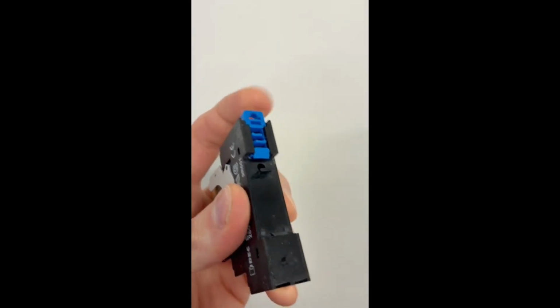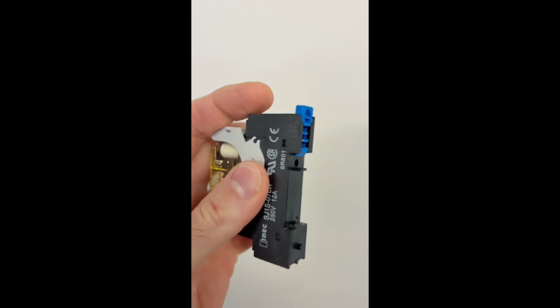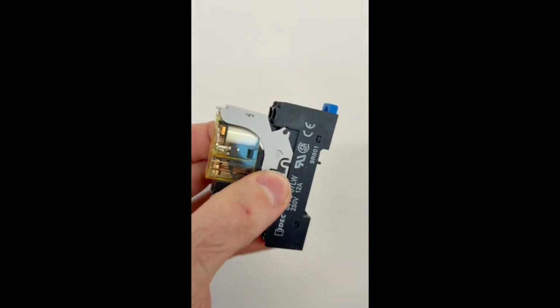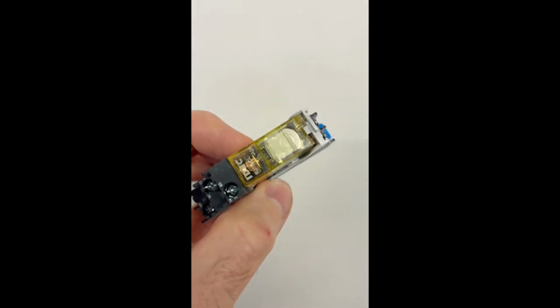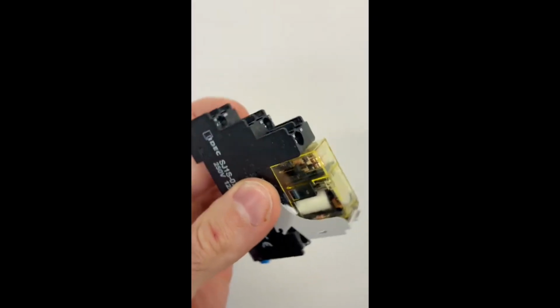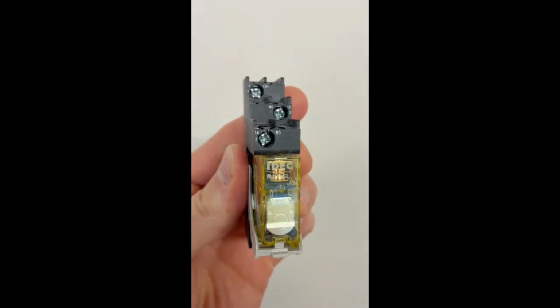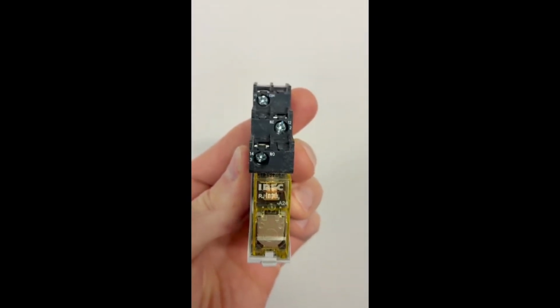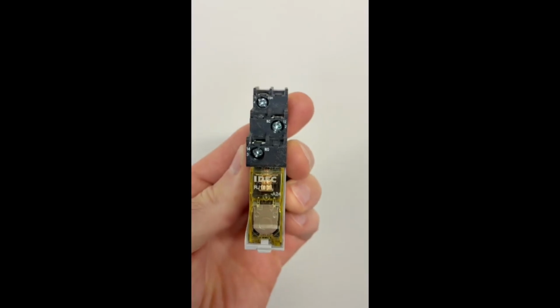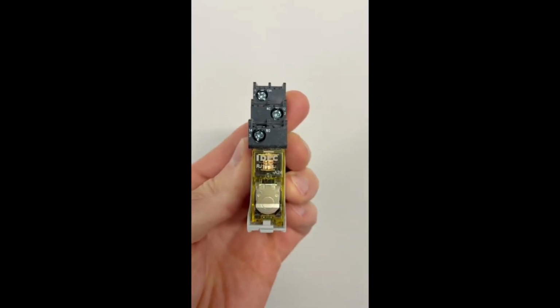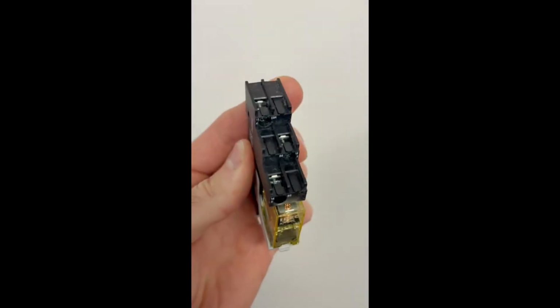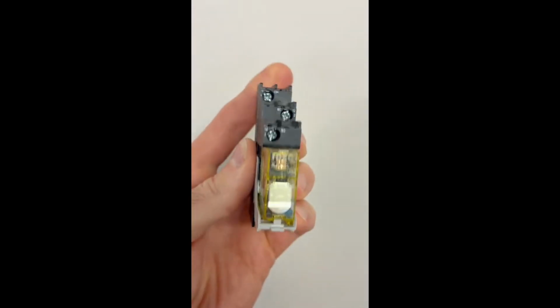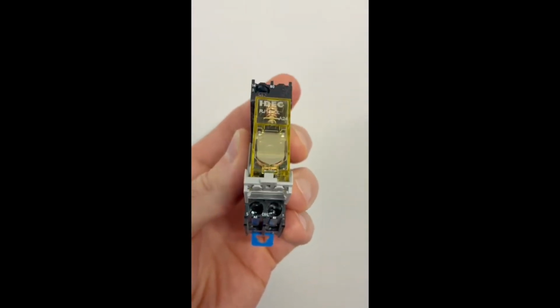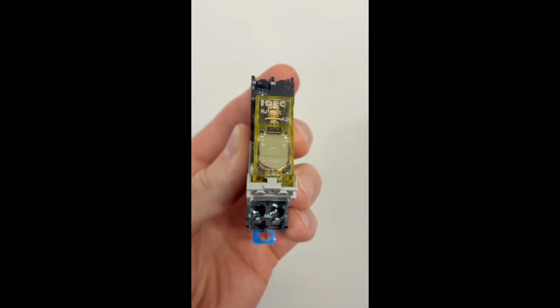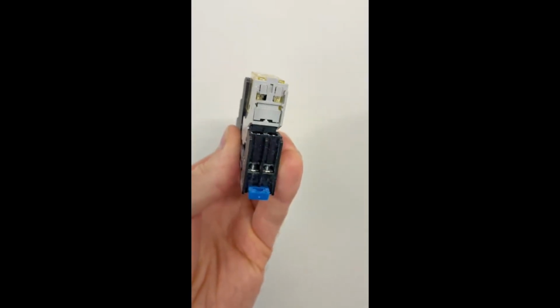And again, it'll attach to DIN rail. So again, when that coil on the relay is energized, it's going to send the 24 volts from the power supply to the VFD to turn on the water pumps. Or it'll just allow, in its resting state, the 24 volt signal from the BAS to energize the VFDs and turn the water pumps on. But again, if the programmable digital timer says, okay, yeah, this is the time frame that we want the pump to be allowed to run.